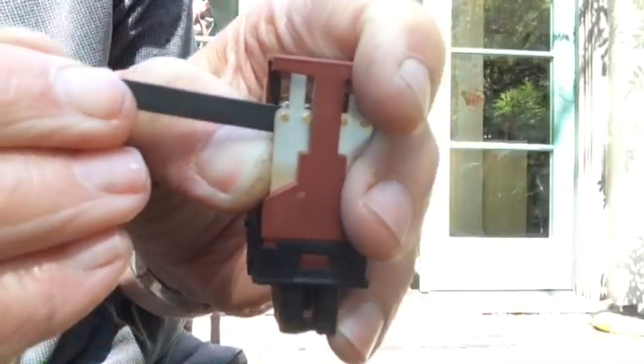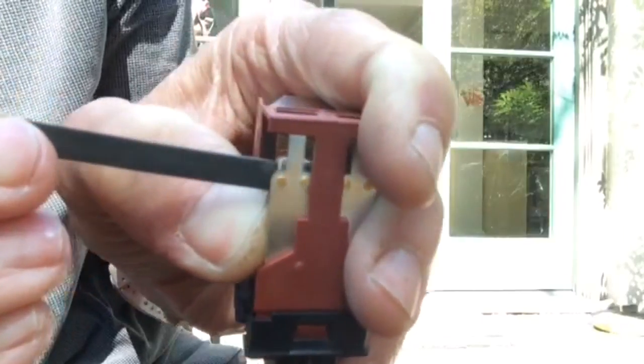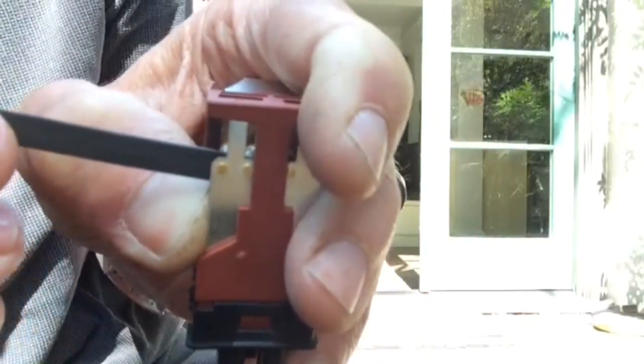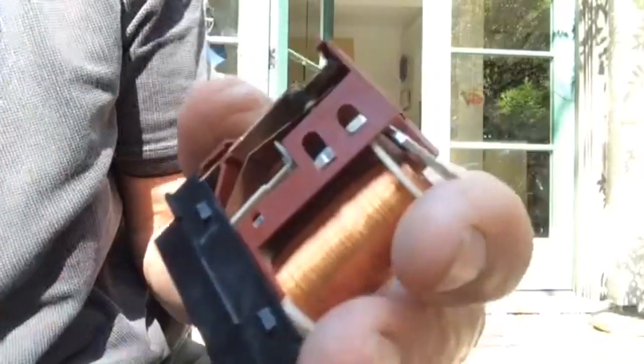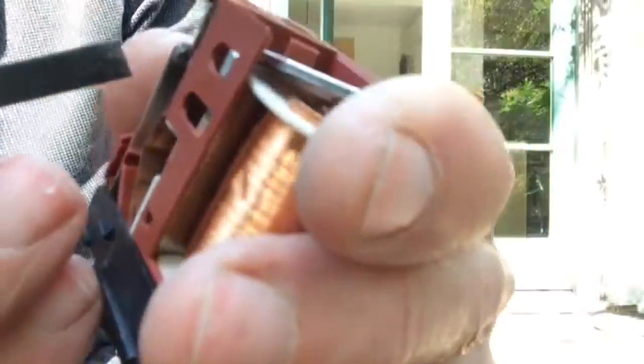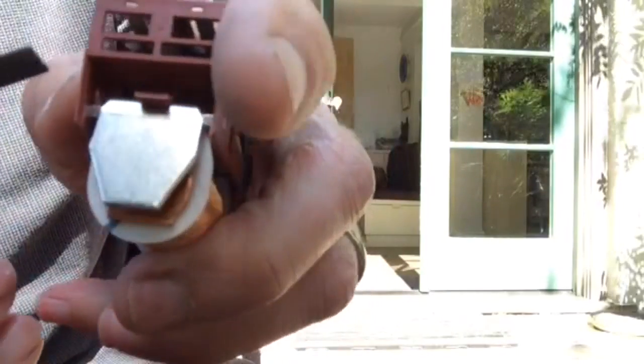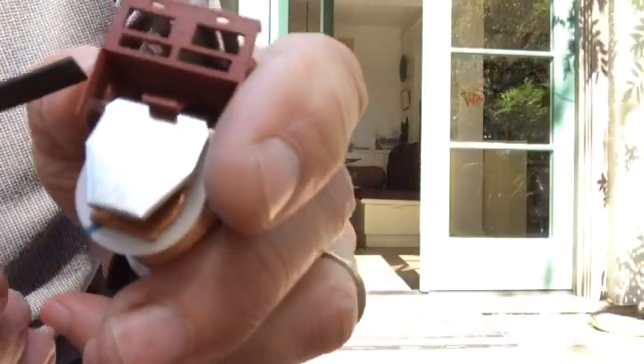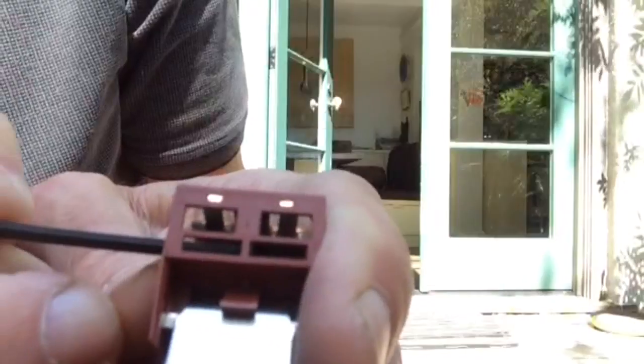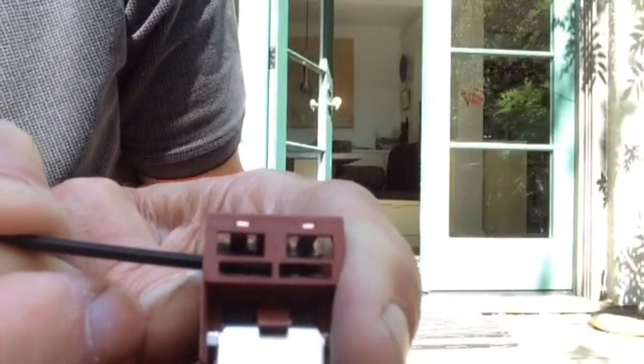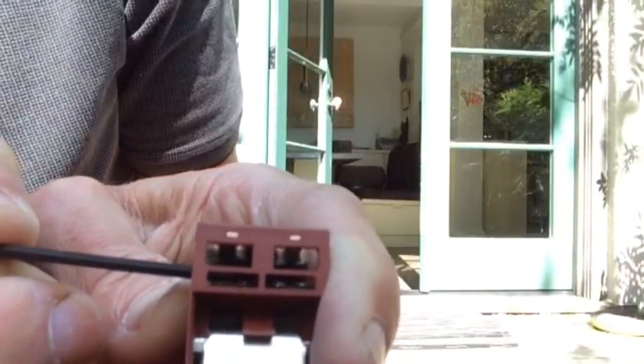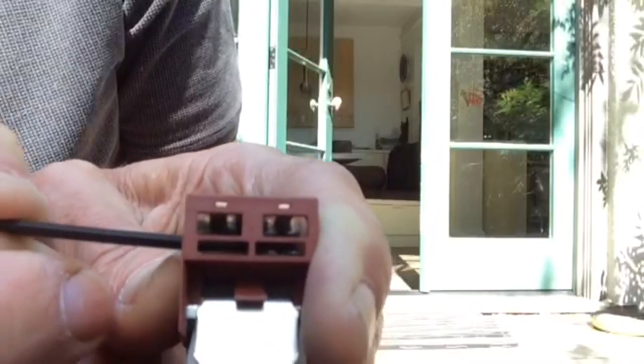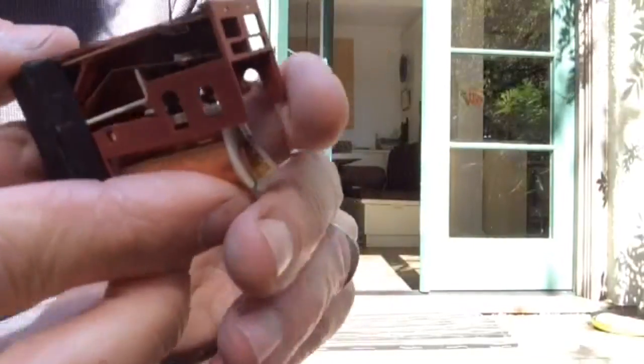Finally, there's so much carbon the electrons can't pass through and the heater won't work. So we're just cleaning up these points again with this flat file. And what you'll notice is there's a total of eight of these little round points. And we've got to clean them all up so they're shiny. So we just take the flat file, go back and forth on them to remove all the rough spots and remove the carbonation. And I would go back and forth maybe about ten times for each one.